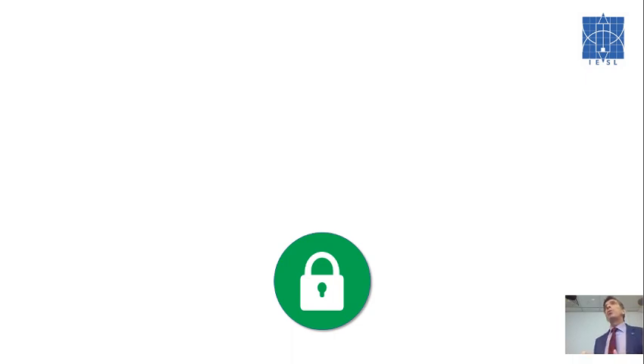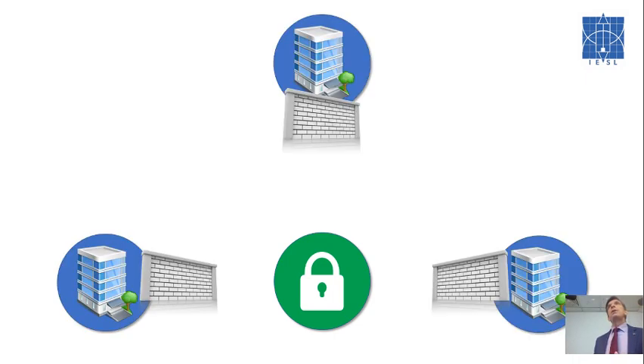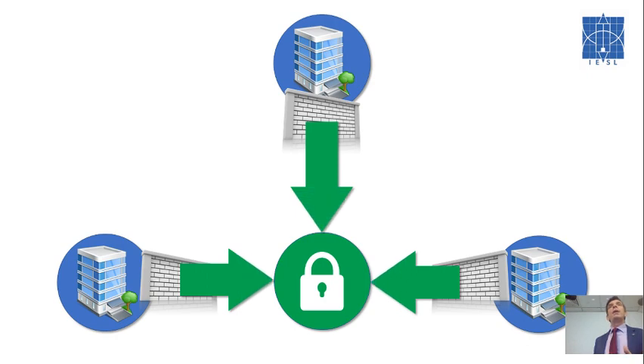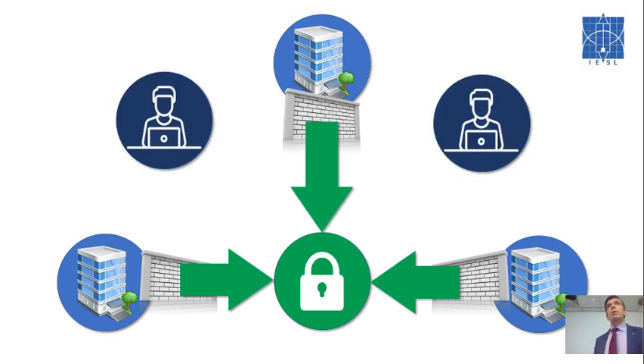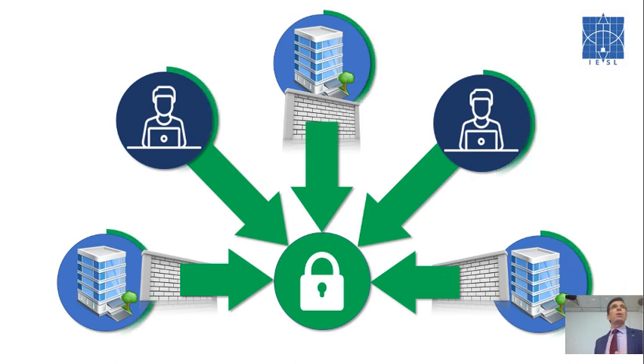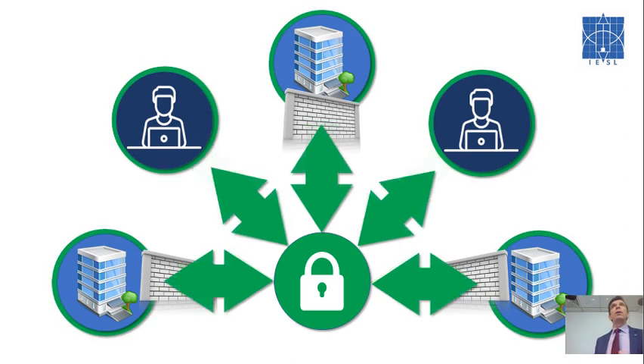So how BACnet Secure Connect works is that it generates connections from inside the building to a secure location, creating a hub and spoke situation, meaning users now come from the outside instead of punching a hole from outside through the firewall. They connect to BACnet Secure Connect, and that connection, once made from the inside out, becomes a secure, bi-directional link.